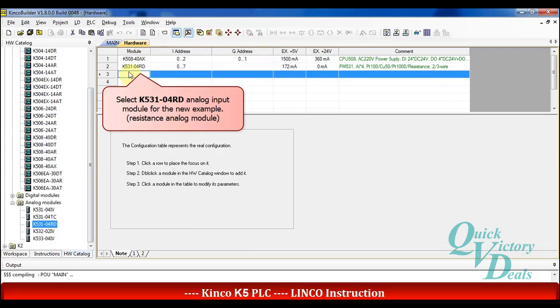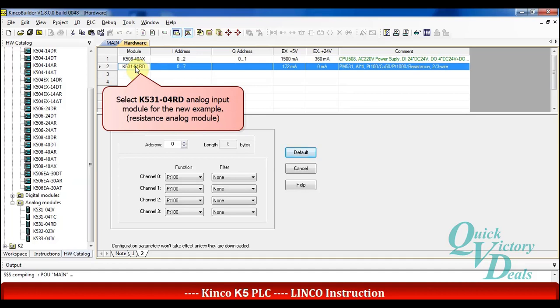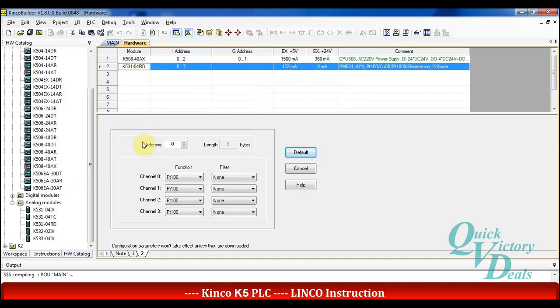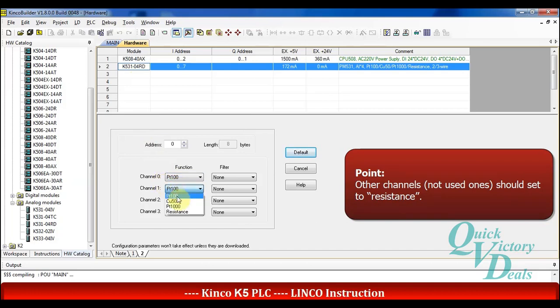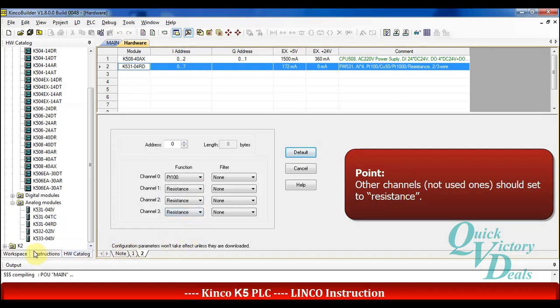I choose the K531-04RD module that supports 4 channels for RTD sensors. I click on it and open the settings. For better performance, we should set the used channel as PT100 and set the other channels to resistance. Then return to the main window.